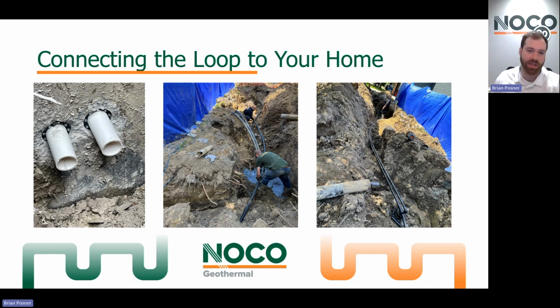So this was actually a larger home that needed 2 boreholes. So 2 500-foot boreholes. You can see the piping popping out of the hole at the bottom of the screen on the right, and it's being connected over to the gentleman in the middle of the screen who's connecting it to the second borehole. Once those pipes are fused and you have both boreholes in series, they will bring that piping over to the sleeves going through the foundation wall, bring the piping into the basement where it then can be connected into the heat pump.